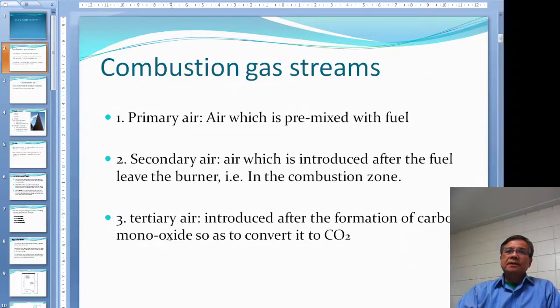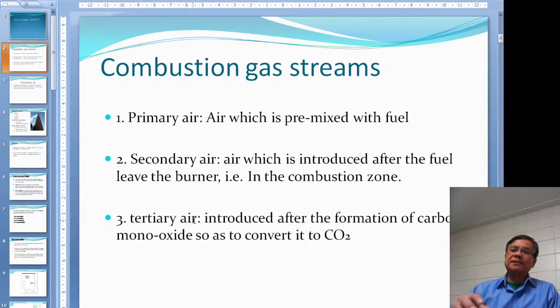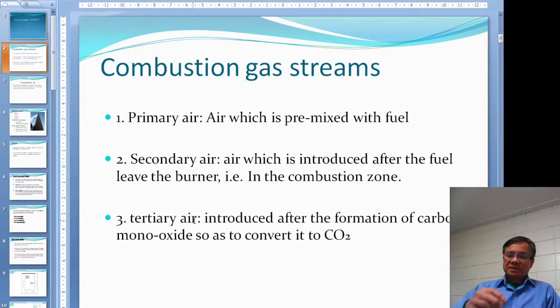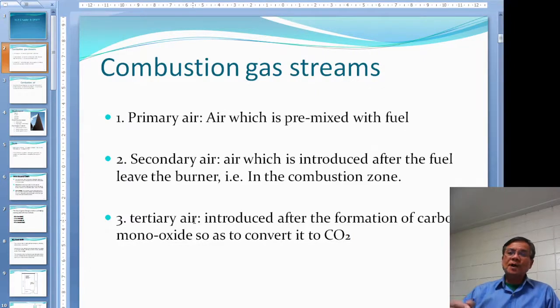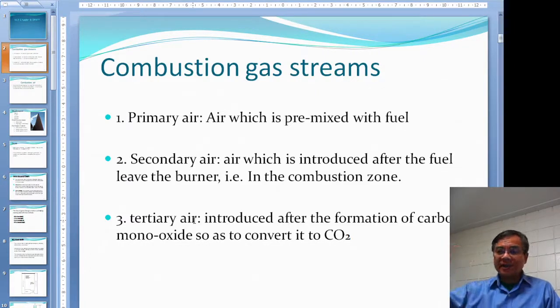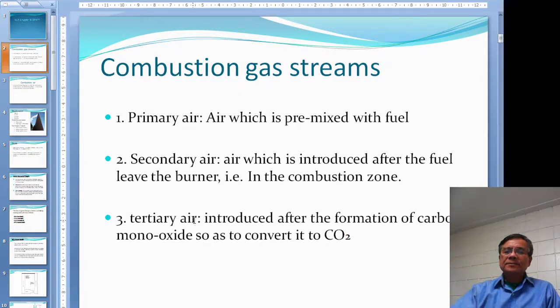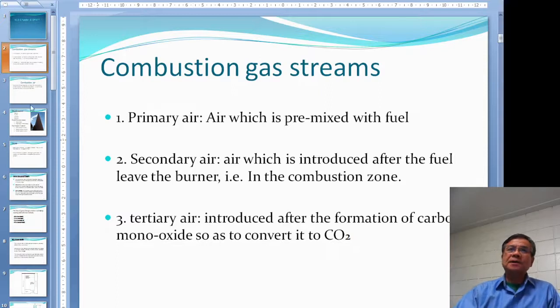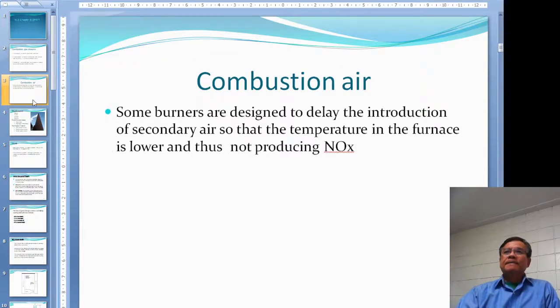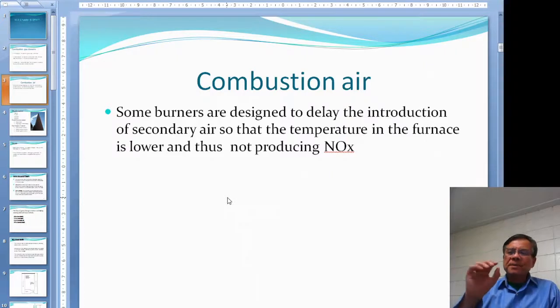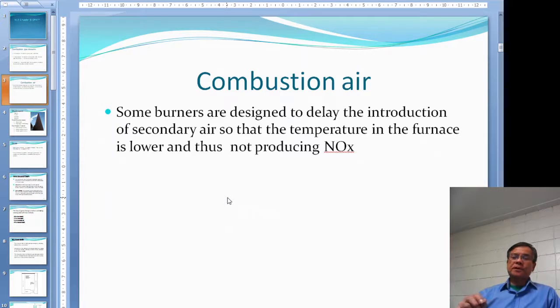Tertiary air is the air you put in after you burn some of the carbon, but the combustion is not complete — it produces CO. You then add some more air at the end to convert the CO into CO2. So the combustion air is introduced in stages due to environmental concerns.